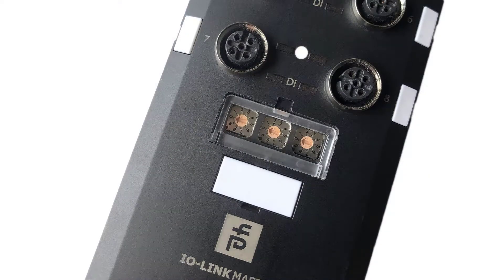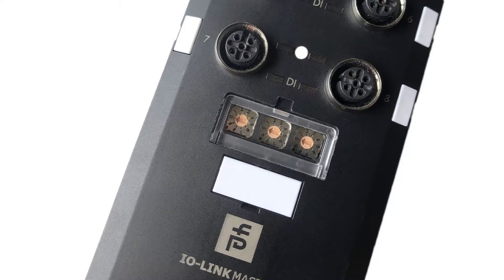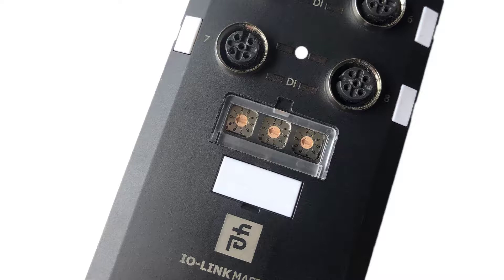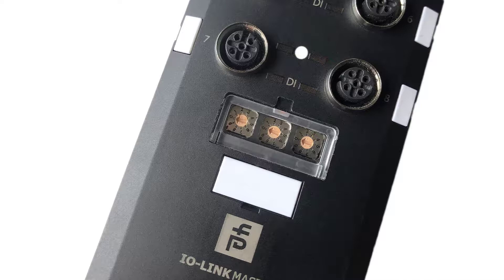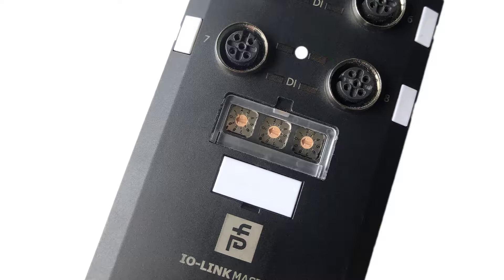Now, if you look at the ICE2 block, you're going to notice that there's three rotary switches on the front. These can also be used to set the lower three digits of the static IP address, which again, by default, is 250. But, this method is usually only used in special circumstances. So, if you've ever had trouble connecting, remember that if the rotary switches are set to a non-default position, the rotary switches override the lower three digits, or eight bits, of the static IP address, which we just configured.